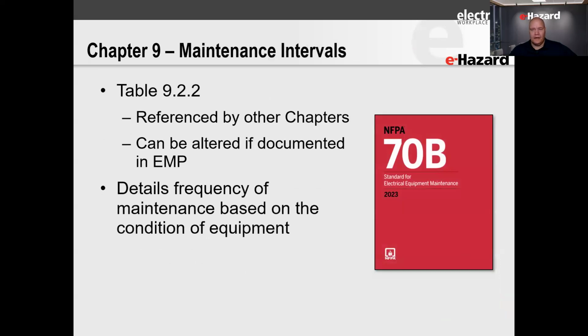Chapter 9 might be the star of the show when it comes to 70B. Unless you have the manufacturer's instructions — if you do, and the equipment's in good working condition, serviceable equipment, default back to those intervals of what the manufacturer is telling you to do.